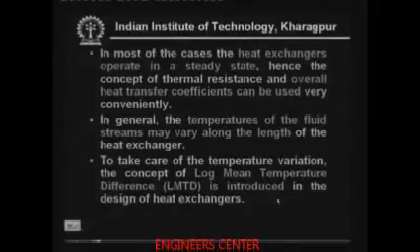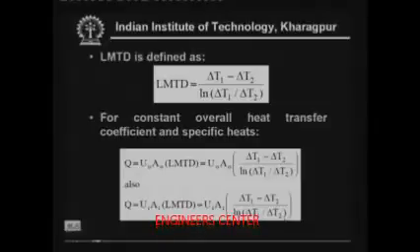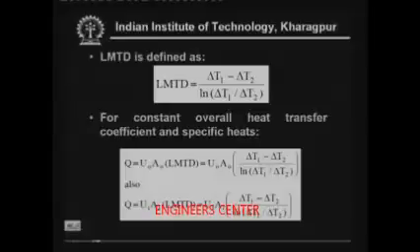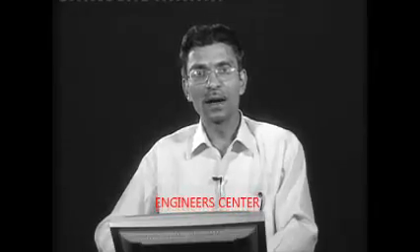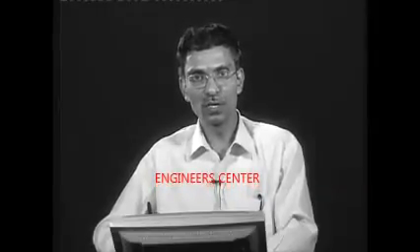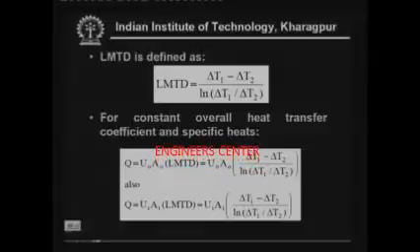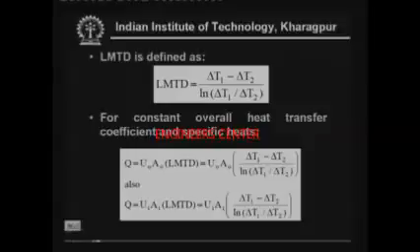This is known as log mean temperature difference or LMTD. LMTD is introduced and very widely used in heat exchanger design. LMTD is defined as LMTD equals (delta T1 minus delta T2) divided by ln(delta T1 / delta T2), where delta T1 and delta T2 are the temperature differences between the hot and cold streams at the inlet and outlet respectively — basically the terminal temperature differences. If you are using LMTD, the heat transfer rate is simply Q equals U times A times LMTD, written as U_0 A_0 or UI AI depending on whether you reference the outside or inside area.